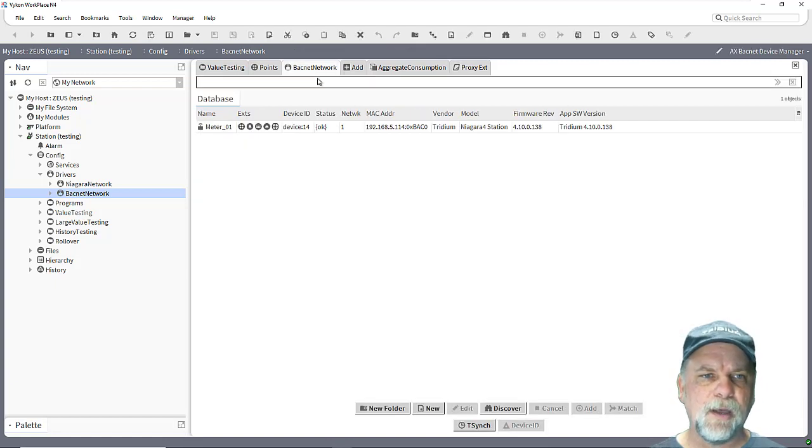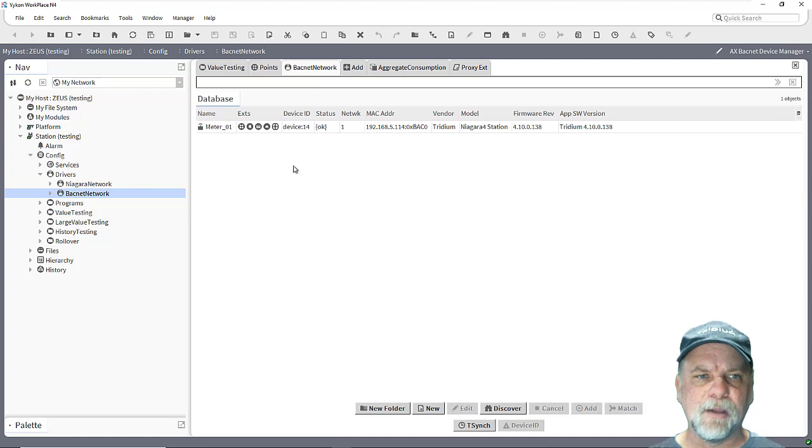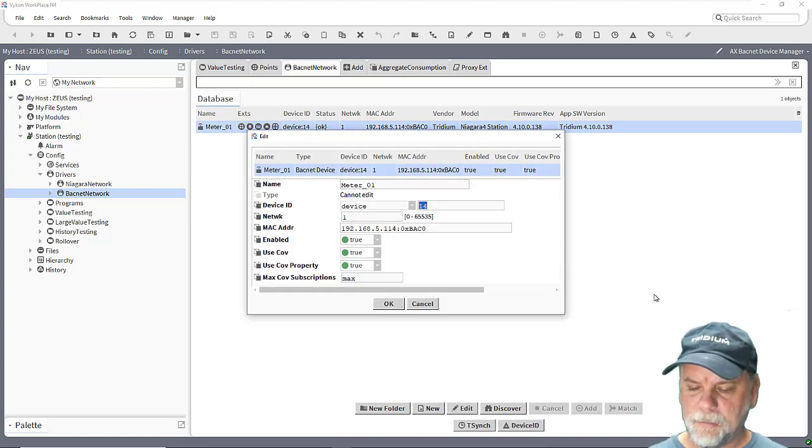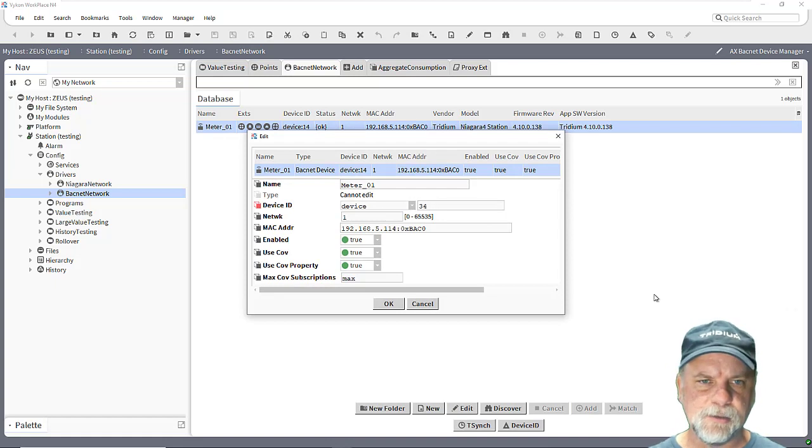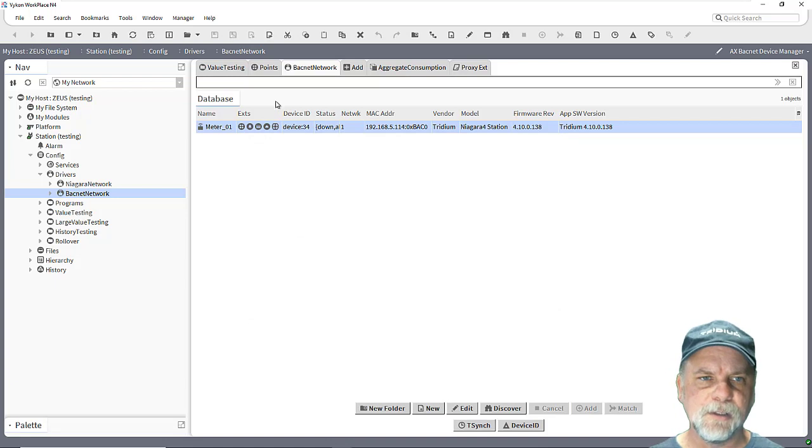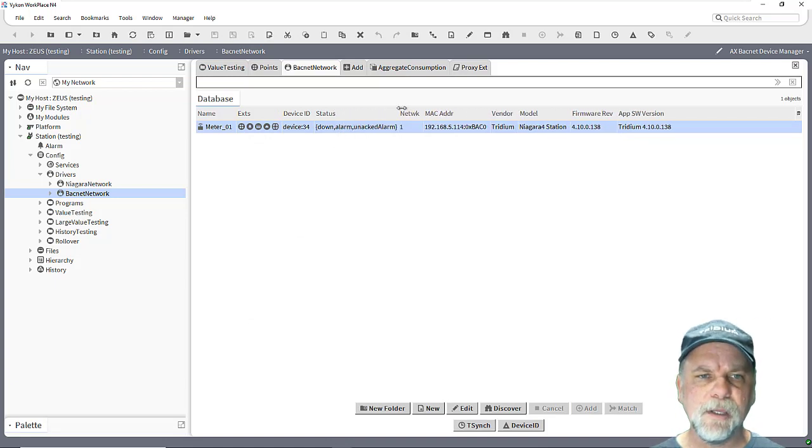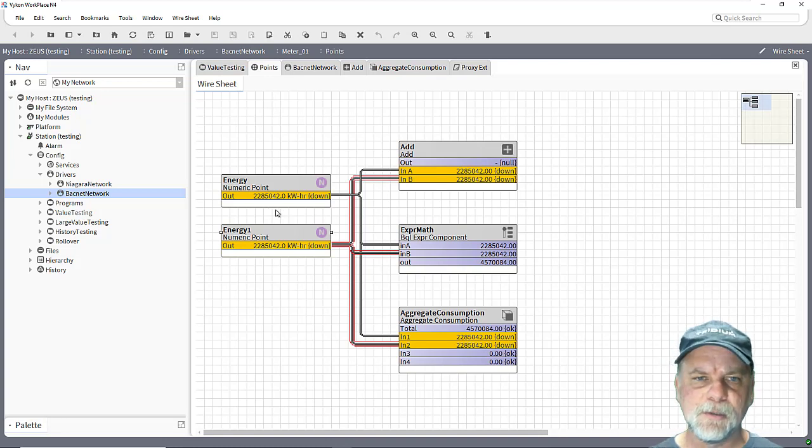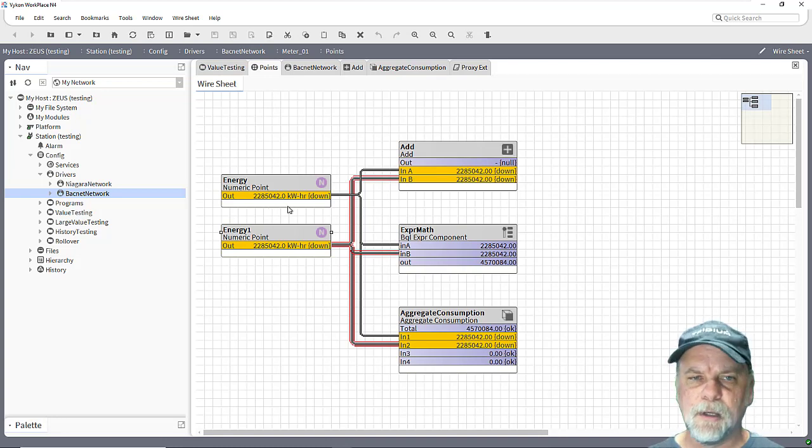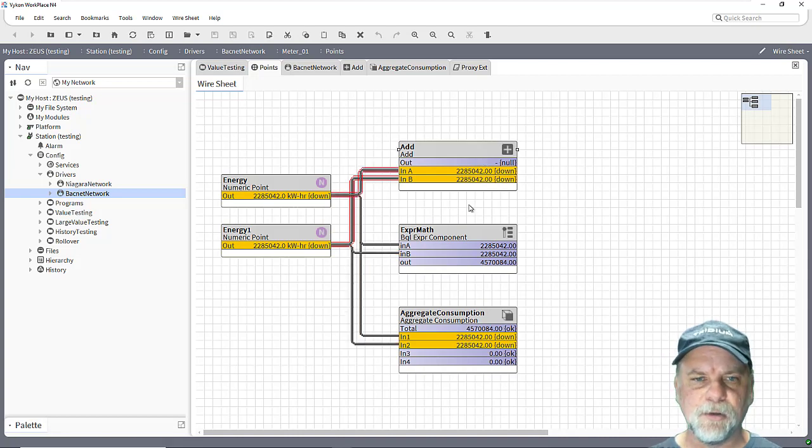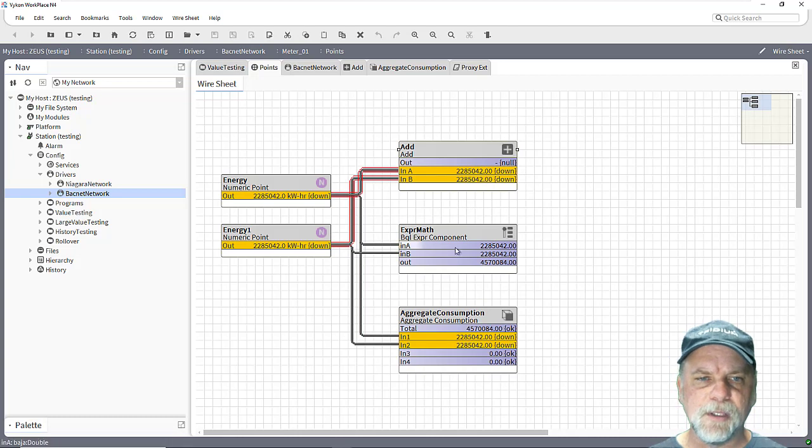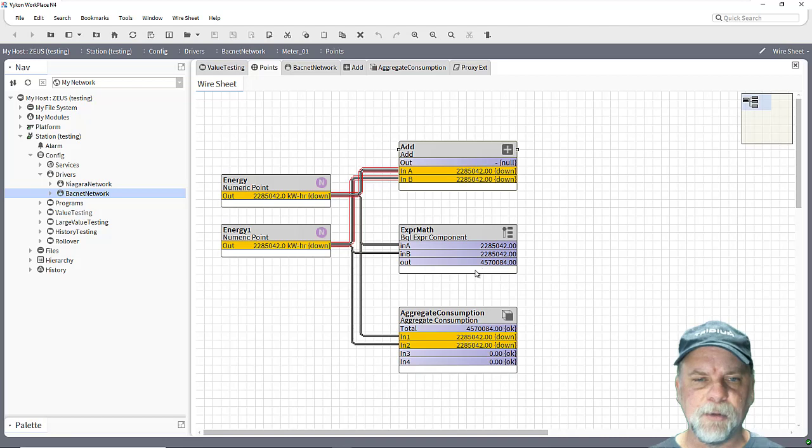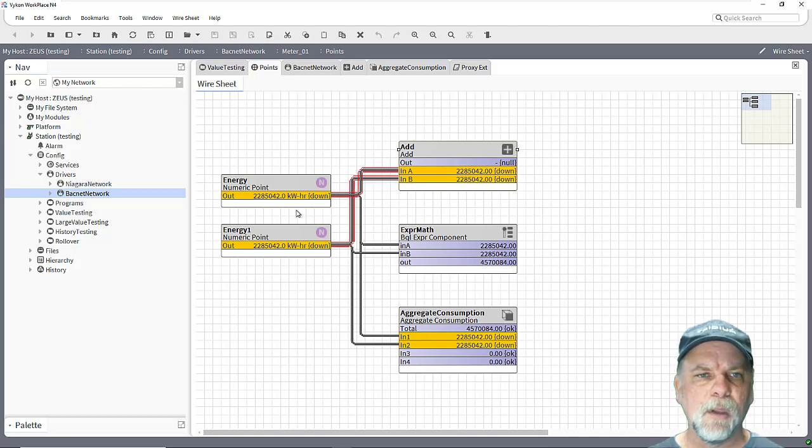To show you how this might impact things, what I'll do is I'll change the device ID here on my BACnet device to something that's not valid for that device, so it's going to cause the device to go down here, get a down alarm, and those points are going to go into a fault status as well of down. So again we realize that the add block in this case has no output because there's no valid input. The expression math block doesn't discount those down statuses so it still has the same number and the aggregate consumption block does as well.